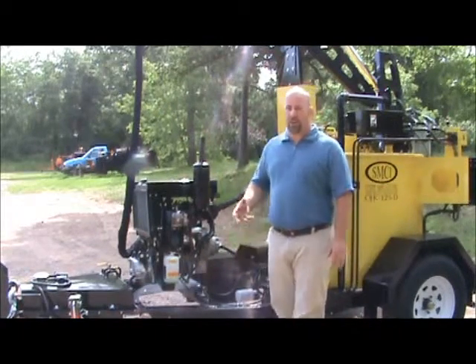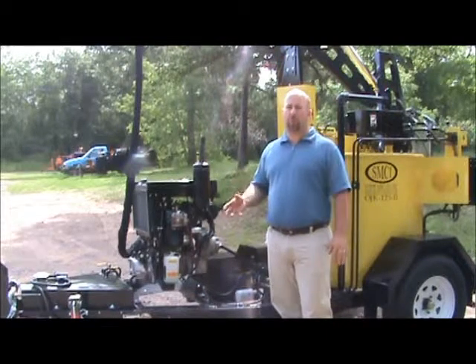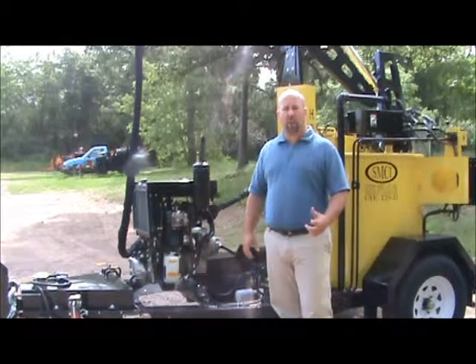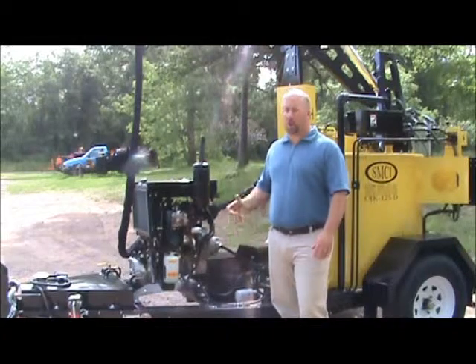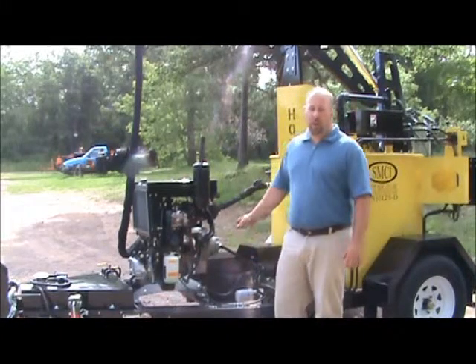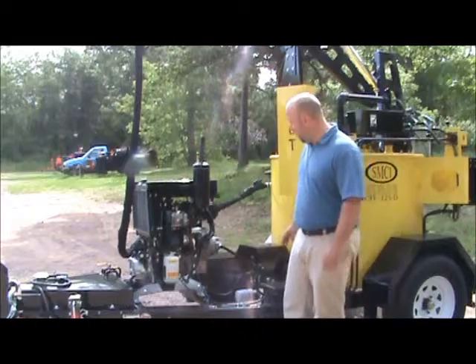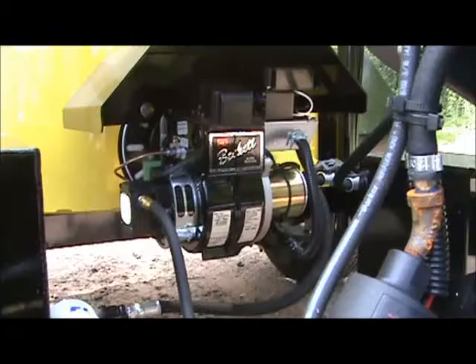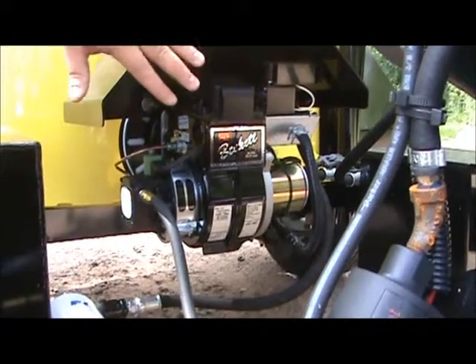Most of the time, if you see a good clean burning burner, we're not going to screw around with it. If we close the air off too much or open it up too much, we're going to run into either burner firing issues or it's going to smoke real bad. So you want a good clean burn out of the burner system. We'll fire that up here in a minute so you can see how that works. This is our burner system here.